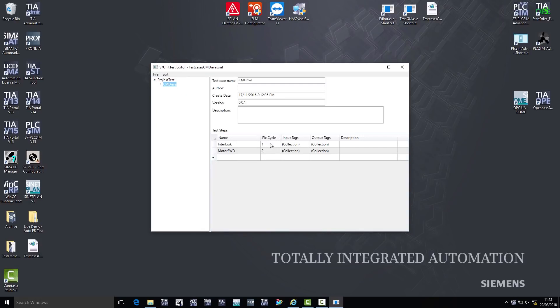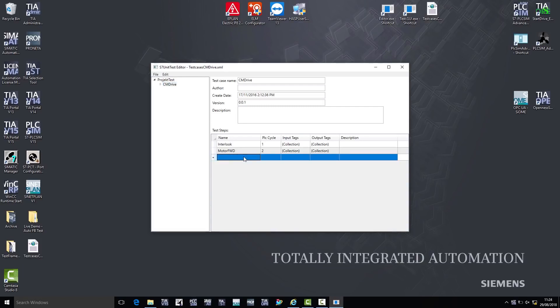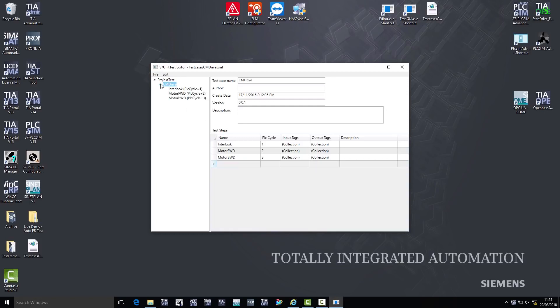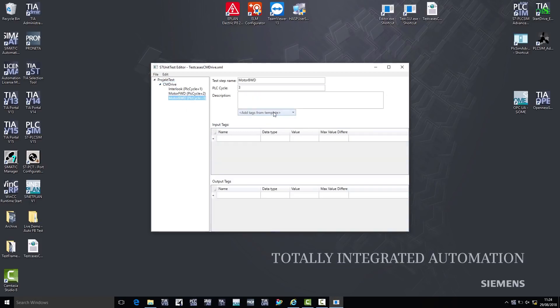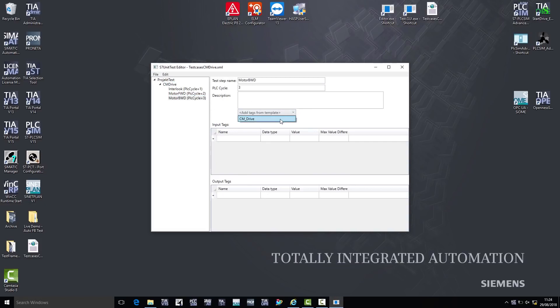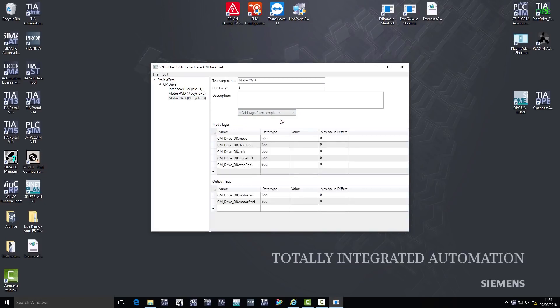There is already a test case for the brake function test, and one to test whether the motor moves forward correctly or not. I now create a new test case, which we want to use to test the move motor backward function. I confirm by pressing Enter, and can now define this test case more precisely. I use the Add tags from template button to import the function block interface from the TIA portal. This means that all input and output tags are listed automatically.